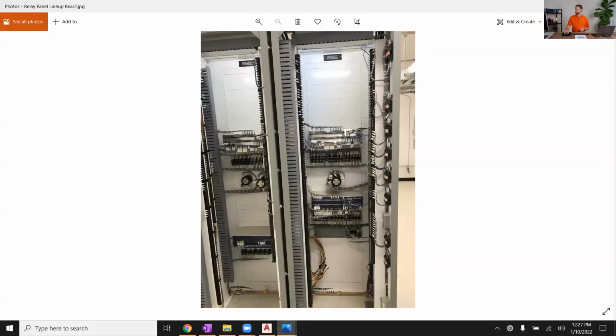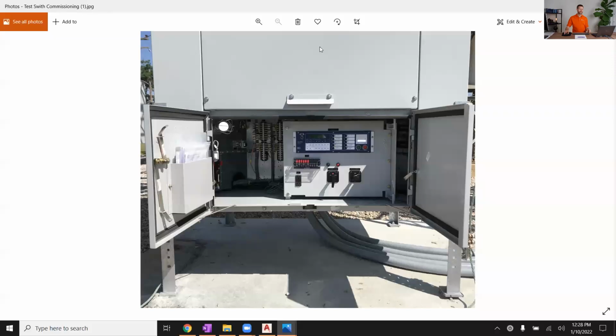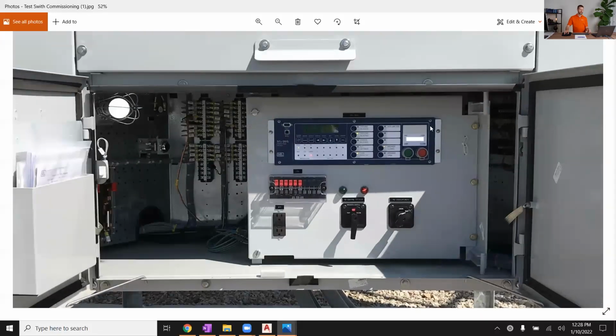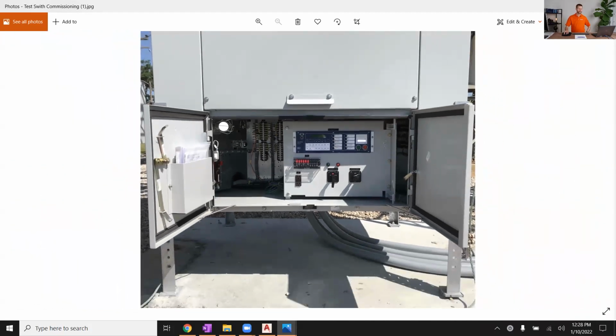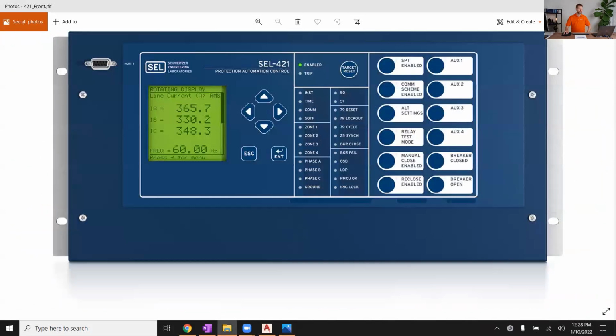But sometimes we don't have the relays in a control house. Sometimes for a smaller substation, they actually mount the relays inside of the circuit breaker control cabinets. And so this would be an example of that. This is a circuit breaker, and inside the breaker is the protective relay mounted in there. It's also got a test switch, control switch, selector switch. We're going to talk about all of these in this design course. So that gives you a perspective of where these relays end up.